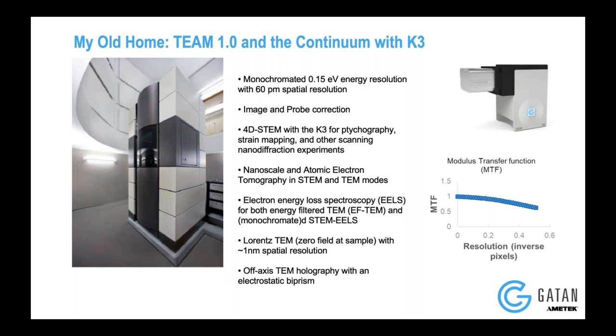To give you context of what that microscope is — it has a monochromator with 60 picometer spatial resolution, it's probe corrected, and it's also image corrected. The cool part about this microscope is that it was recently installed with the Gatan K3 detector, and it was installed in a very unique way. Most detectors are just directly below the HAADF detector, but here the K3 detector was actually at the back end of the spectrometer, so we got the advantage of using K3 for our EELS experiments as well.